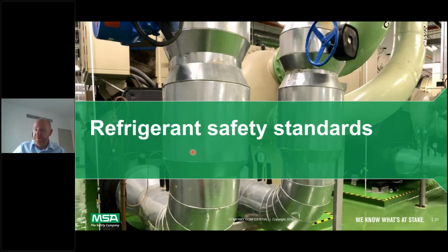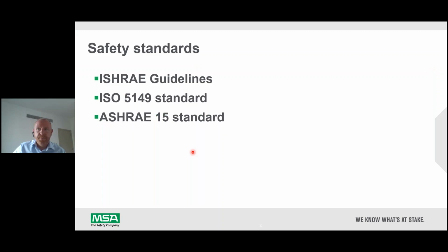So for refrigerant safety standards, there are 3 main standards. We have the ISHRAE guidelines, then we have the ISO 5149 standard about refrigerant safety, which is based on EN 378. And then we have the ASHRAE 15 standard, which also links into ASHRAE 34. ASHRAE 34 describes the refrigerants and gives the safety properties of the gases.